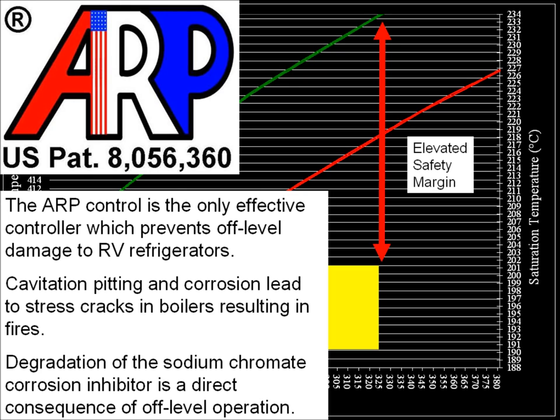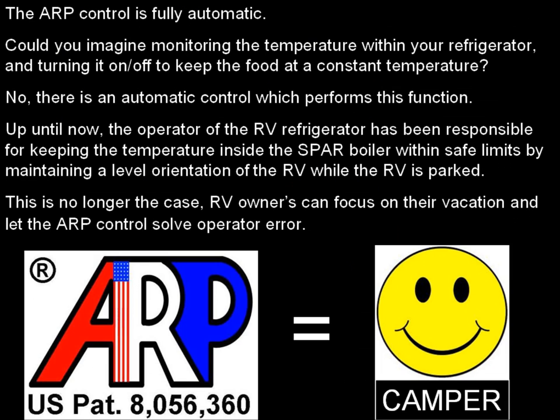The ARP control is the only effective controller which prevents off-level damage to RV refrigerators. Cavitation pitting and corrosion lead to stress cracks in boilers resulting in fires. Degradation of the sodium chromate corrosion inhibitor is a direct consequence of off-level operation. The ARP control is fully automatic. Up until now, the operator of the RV refrigerator has been responsible for keeping the temperature inside the spar boiler within safe limits by maintaining a level orientation of the RV while parked. This is no longer the case — RV owners can focus on their vacation and let the ARP control solve off-level operator error.